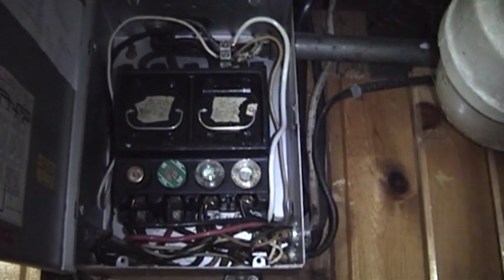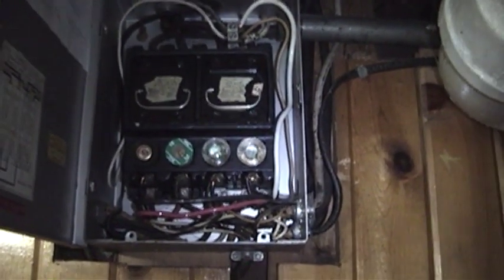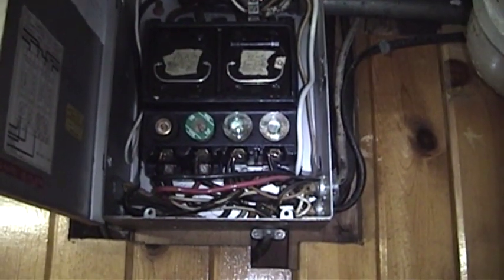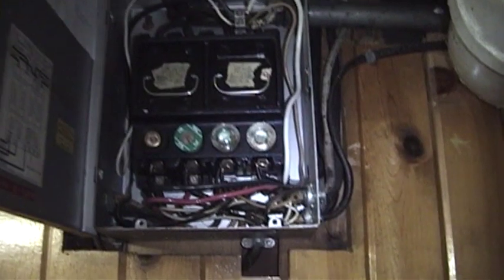While we were in here working, we disconnected all the wiring and took the block out. We gave it a complete R&R — cleaned the contacts, coated them with antioxidant, gave everything a fresh shine. That was around 2001 when we had this big breakdown.